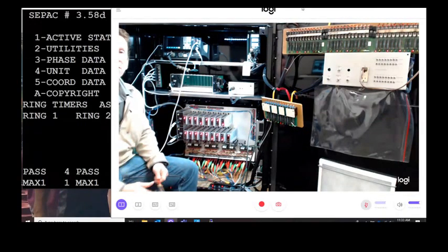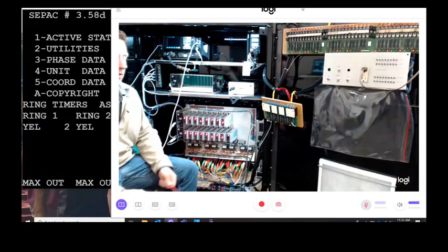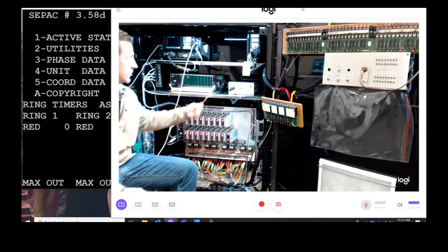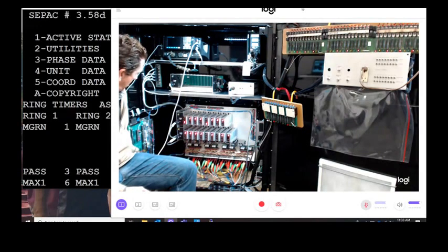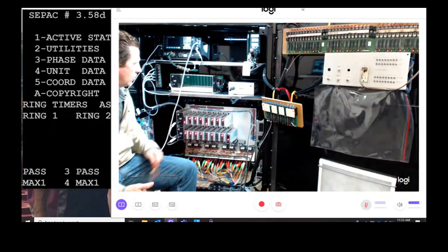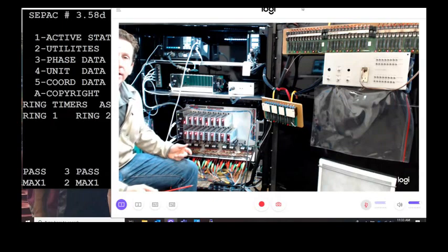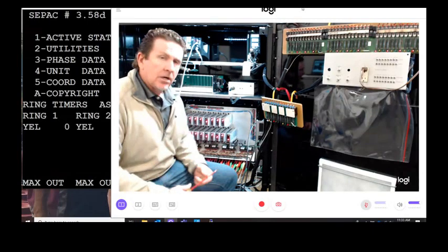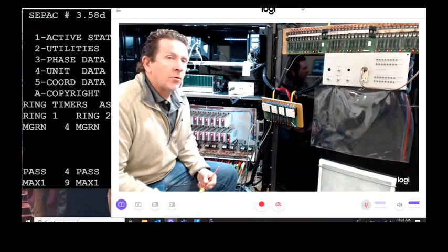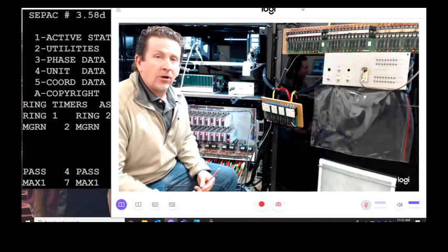This is where it kind of gets a little more involved. Because technically we still have 24 volts in the cabinet, now we've lost it from the back panel to the side panel. So we either have a wire that's broken, or some folks have been lucky enough to be involved in changing out the L board on the back panel.